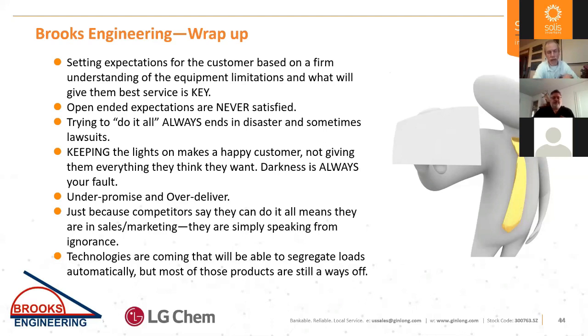That's all I can say about that, is that there are large companies out there right now doing whole house backup with equipment that is absolutely not capable of providing whole house backup. Exactly. And then they have documents that say, yes, if you plug too much stuff into this thing, it's going to crash the inverter, and we've notified you of that, and they wash their hands of it. And then they tell me that they don't have problems in the field, and I tell them the reason they don't have problems in the field is because they've never had power outages where their systems are.